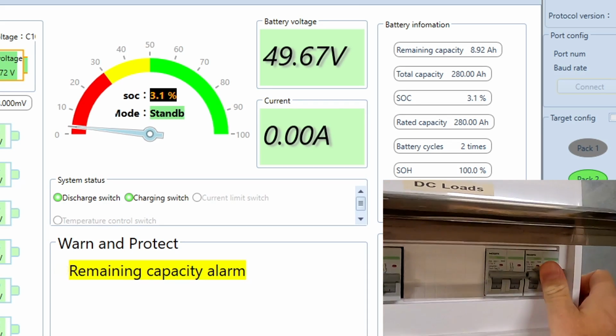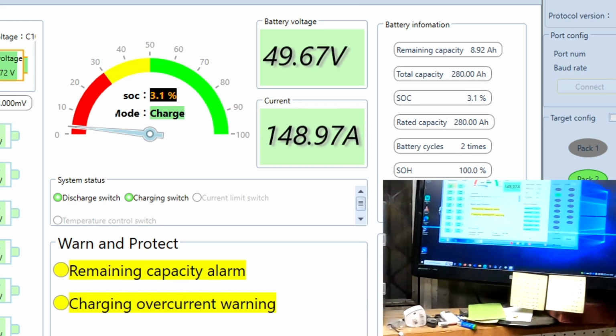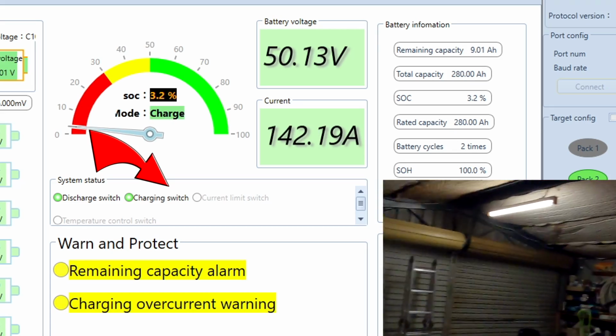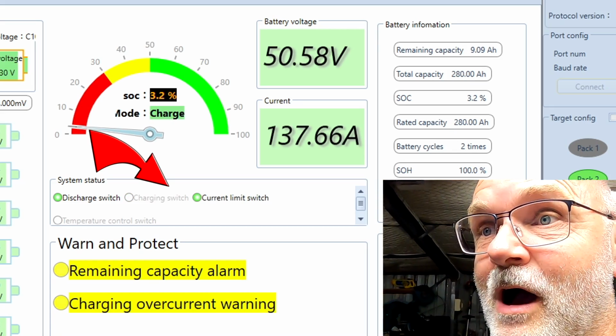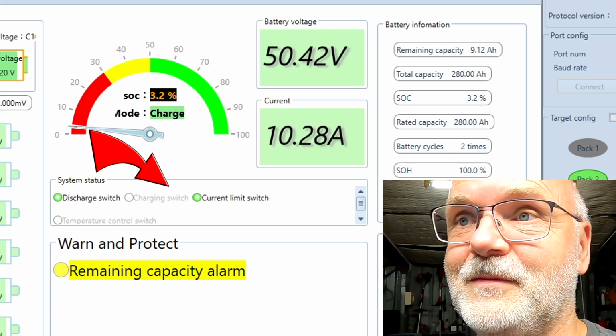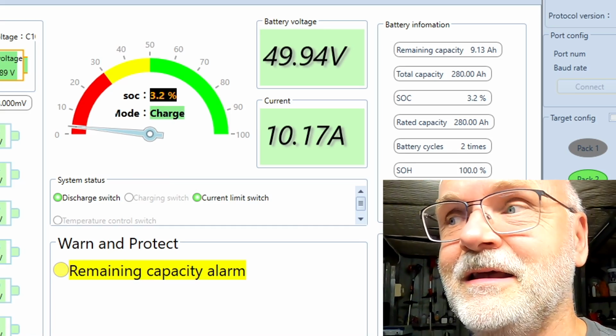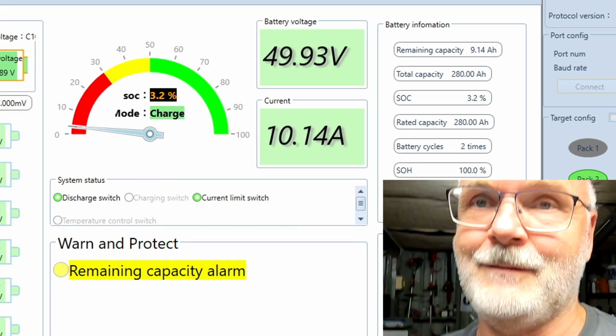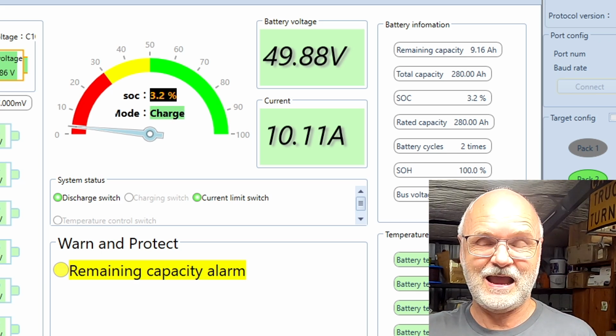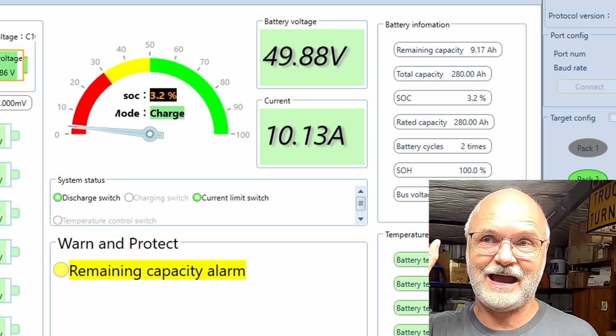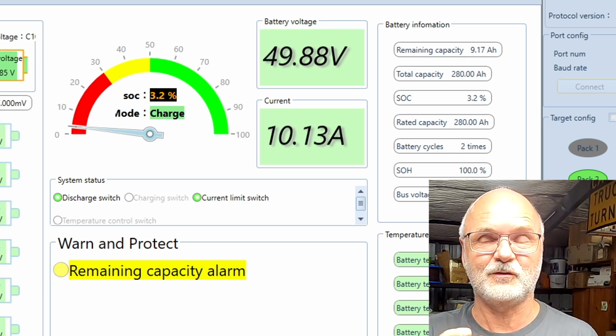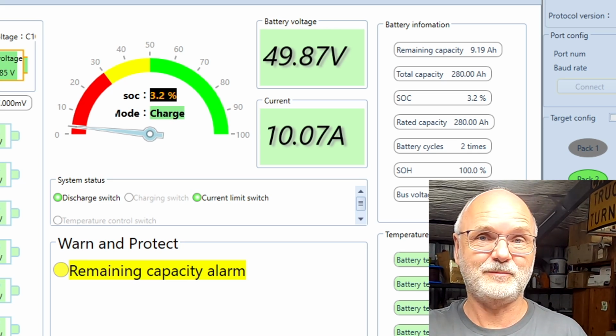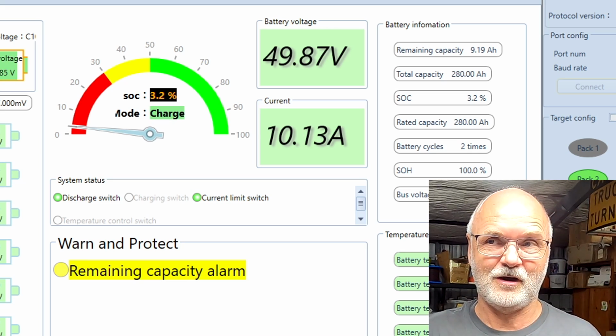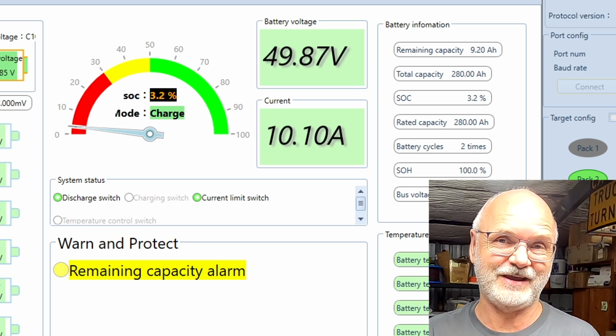3, 2, 1, go. It is on, it is holding 150 amps. Wow, that is okay. Now here it goes, the current limiting switch has kicked in and limited the current to 10 amps. So all these inverter BMSs have a current limiter, and you can set either the overcurrent protection or warning. Instead of the BMS turning off charging altogether, it limits the charging to 10 amps.